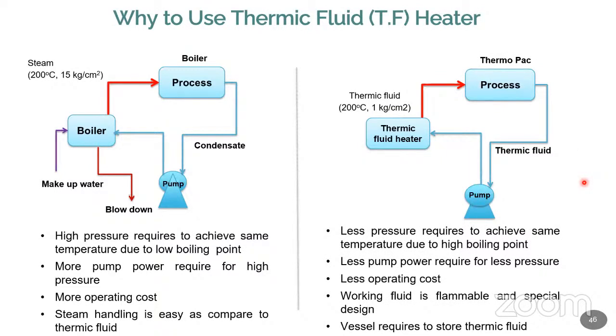Okay, now you can see there is no condensate in the TFH. In the boiler, you have makeup water. Water is made available, and blowdown water is taken out. And we have a separate pumping system to return the condensate to the boiler, and we have makeup water. All the water will be boiled, given to the process, and, sorry, this is not the boiler, this is the boiler process. And again, it starts condensing. So this is the operation.